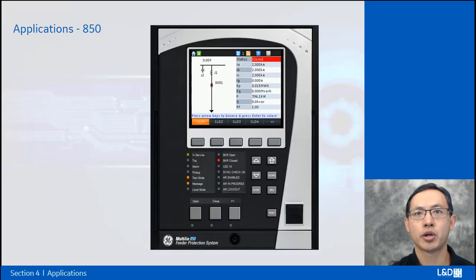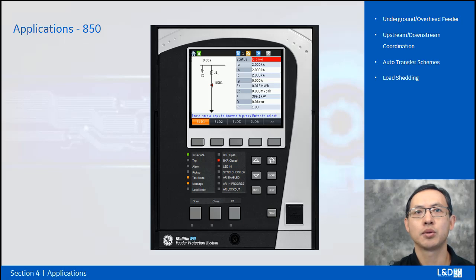850 is an advanced feeder protection relay used to provide primary or backup protection for underground and overhead feeders. With protection and control logic, 850 allows for simplified coordination with upstream and downstream devices. Additional control features such as auto transfer schemes, load shedding, cold load pickup, and auto reclose are also available for the optimal protection and control of industrial and distribution network. 850E is designed for industrial users, 850D is designed for distribution users, and 850P is designed for pad mount RMU protection and control system.